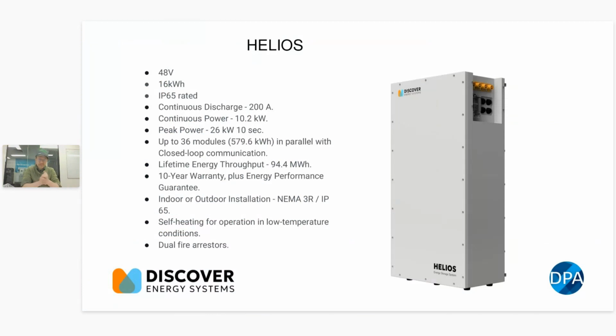In terms of the specs of the battery, it's a 48-volt nominal battery. It's a lithium ferrophosphate battery, 16 kilowatt hours, and 16 kilowatt hours usable as well. It's IP65 rated, but as I'll explain in a moment, it's currently only CEC approved for indoor use, even though it has an IP65 rating.